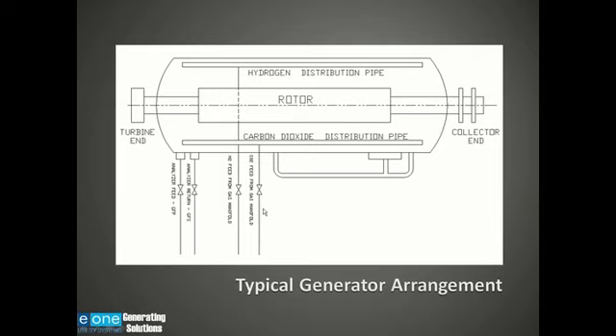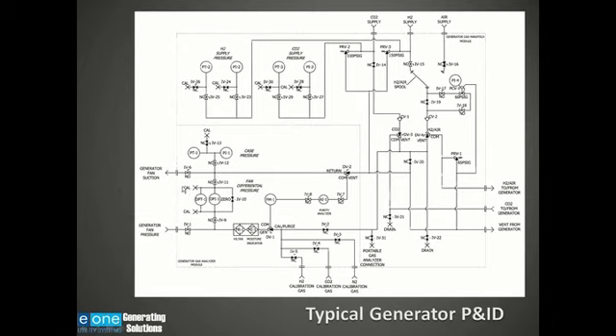One of the things I would like to point out on this slide, as you can see, I have my analyzer feed and my analyzer return. This is generator fan pressure, generator fan suction. This is where I will take a sample when the generator is spinning, when I have a differential pressure. When I don't have a differential pressure, then I've got to rely on case pressure again, take the analyzer to vent, and the case pressure will create flow through my analyzer.